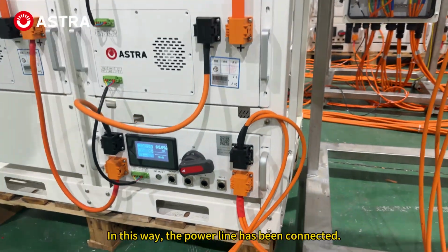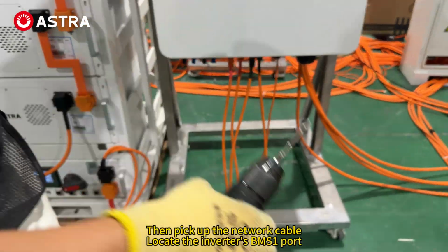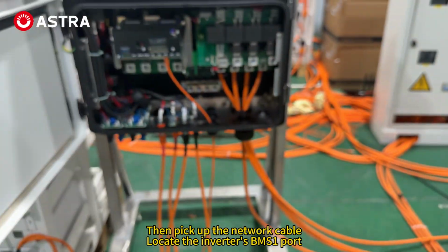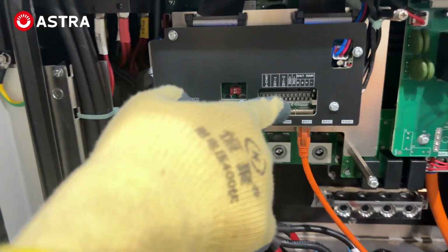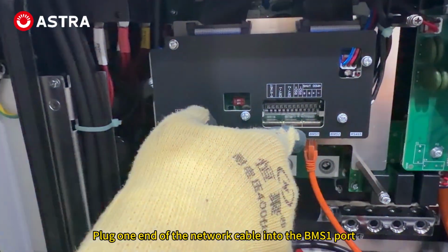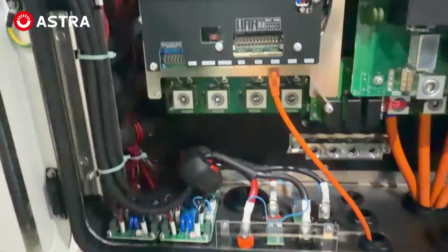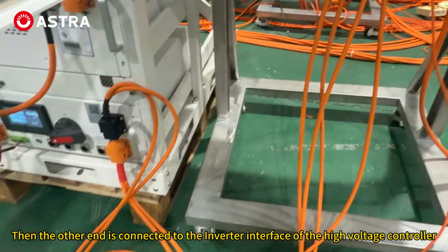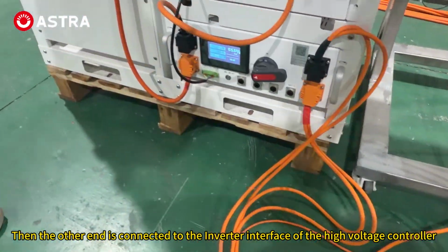In this way, the power line has been connected. Then pick up the network cable and locate the inverter's BMS1 port. Plug one end of the network cable into the BMS1 port, and connect the other end to the inverter interface of the high voltage controller.